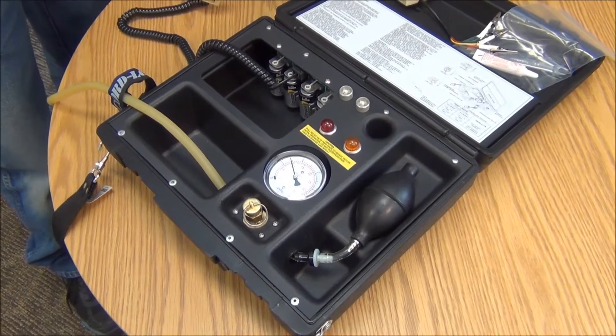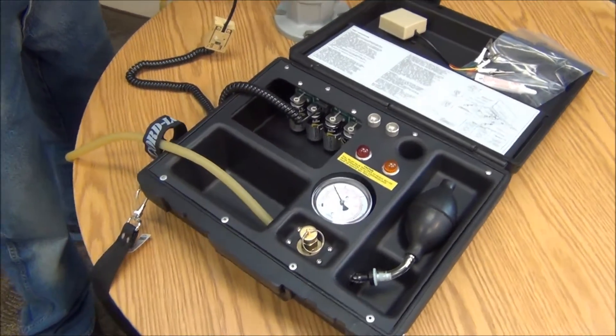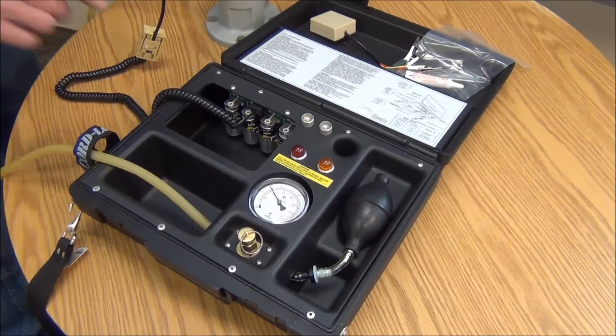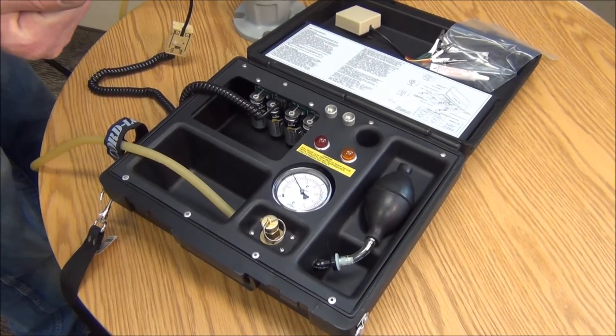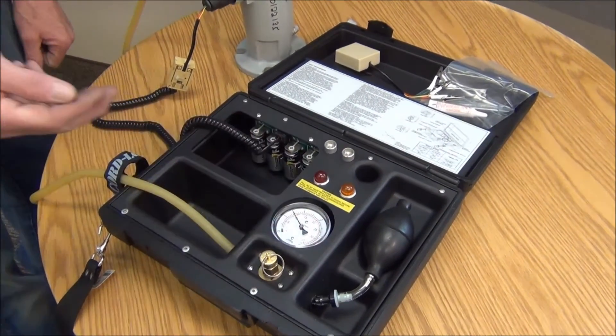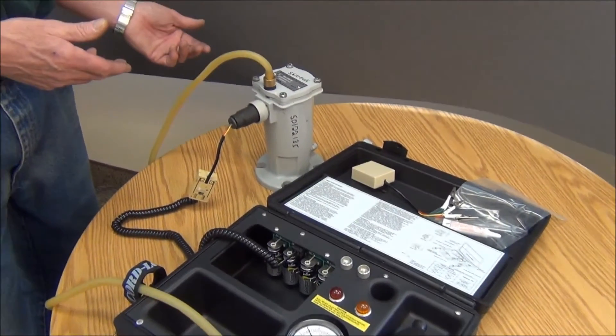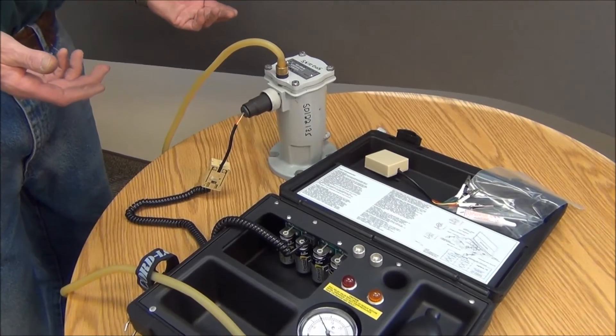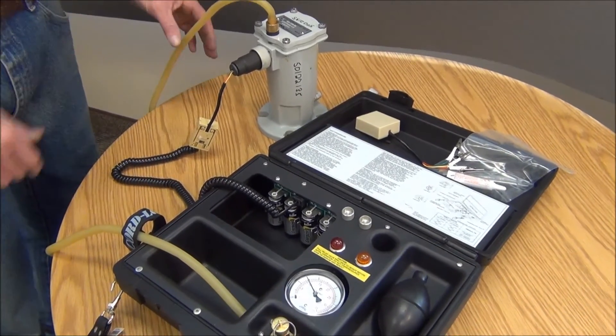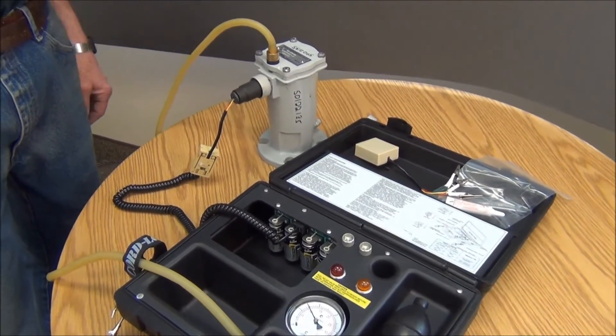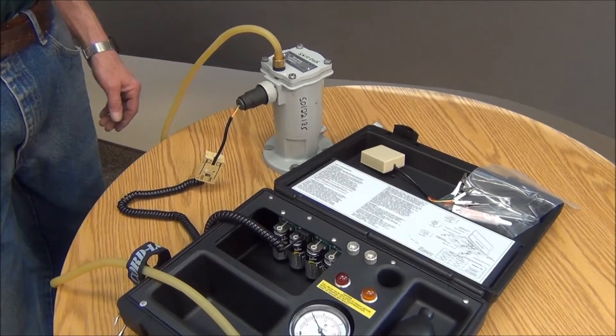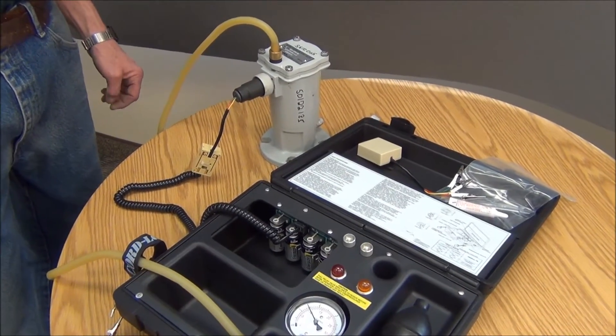What this is going to simulate is a slow rate of rise. When we relieve the pressure this time, we don't want that yellow light to trip. This would simulate a false trip on a transformer - it simulates a low rate of pressure rise.